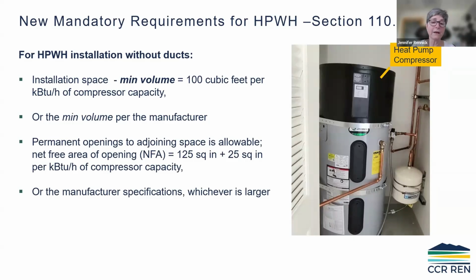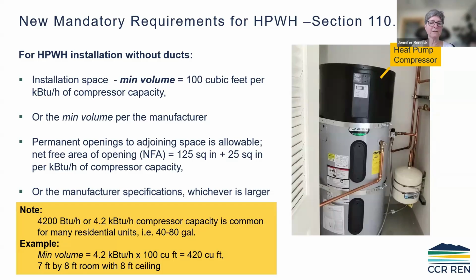So then there's a net free area calculation that needs to go with it, also based on the compressor capacity or the manufacturer's specifications. Where this comes into play is that a lot of this is really the plans examiner's wheelhouse, because these aren't necessarily requiring HERS or ECC, but somebody somewhere, the designer, the mechanical engineer, should design the space properly. But at least you have a place now to go to in the code to take a look at it. And as a rule of thumb, a lot of the compressors are 4.2 kBTU per hour, and some of them are 4.5 kBTU per hour.